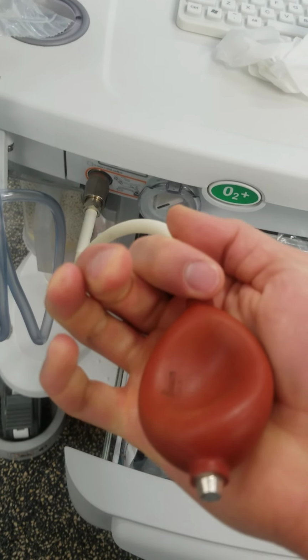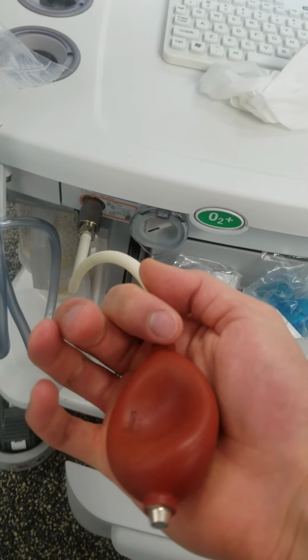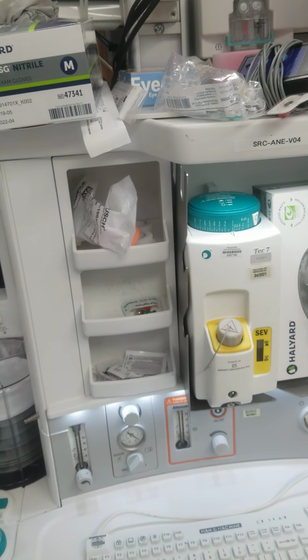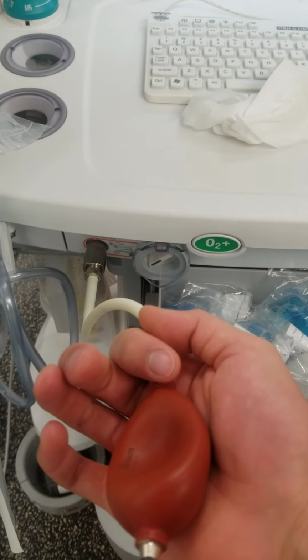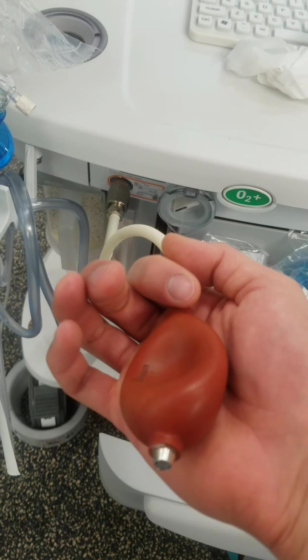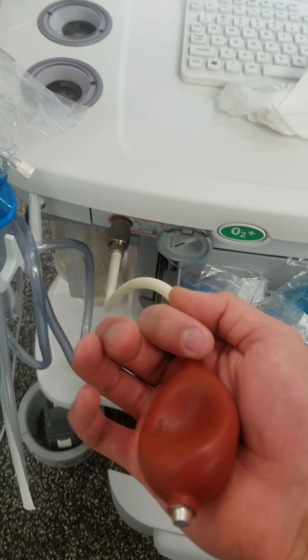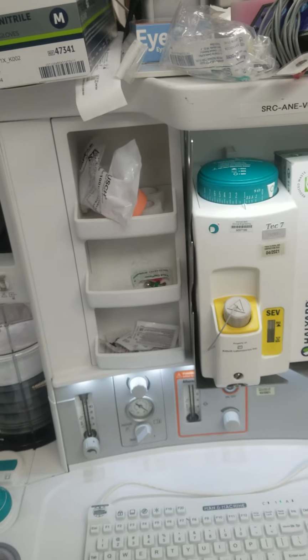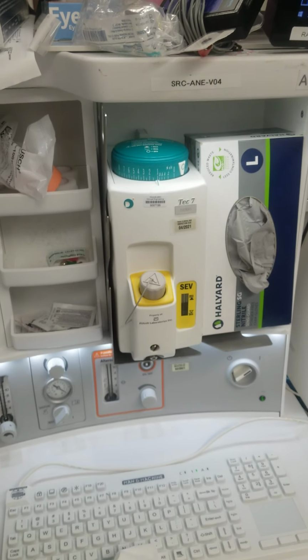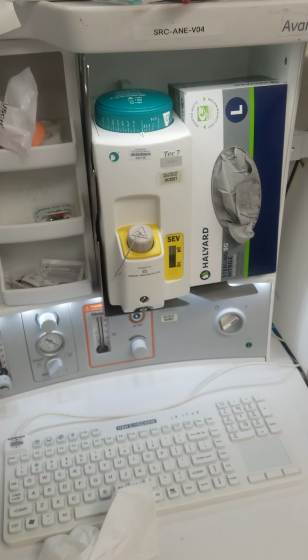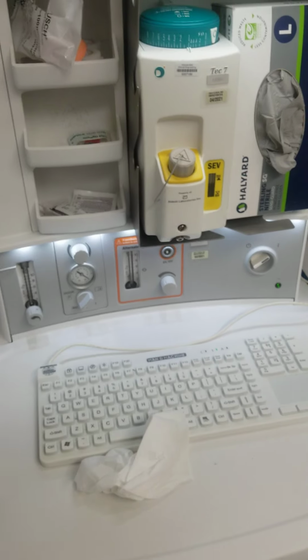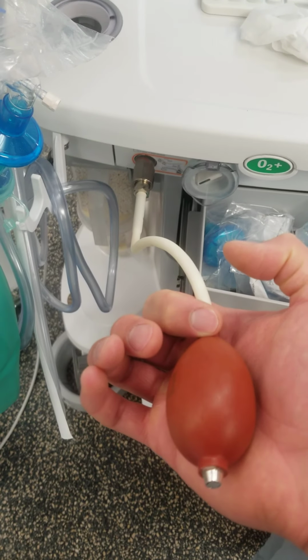Hopefully it holds the suction. It should last for about 10 seconds. Remember, I've got 1% on the Sevo, and I've got the bulb down to suction here. Some people will do this before they open up the Sevo to 1% and then see if it holds and then open up the Sevo. What that does is it eliminates whether the leak is involved with the vaporizer or not. But if you have no leak with the vaporizer open, then you know the whole circuit's good. So that's my little trick.